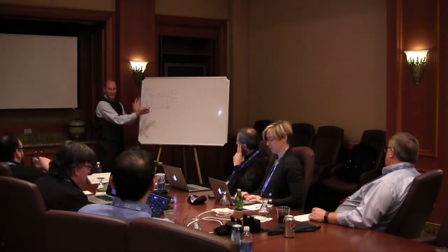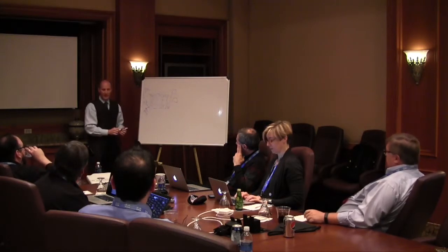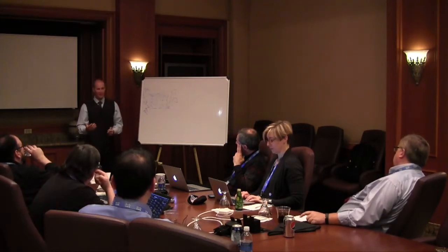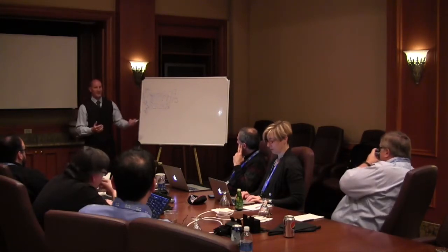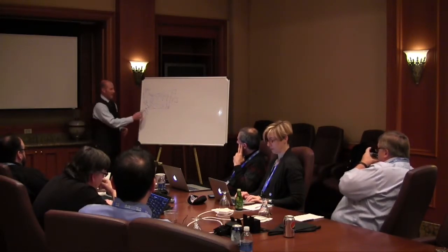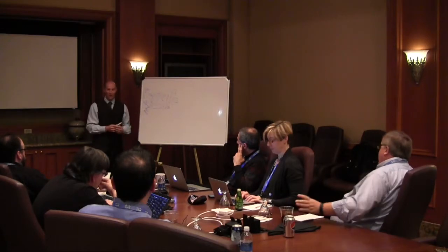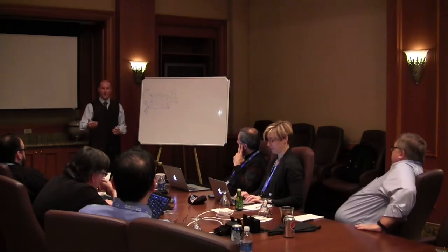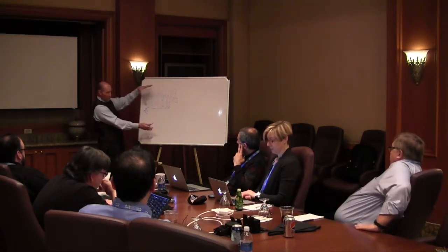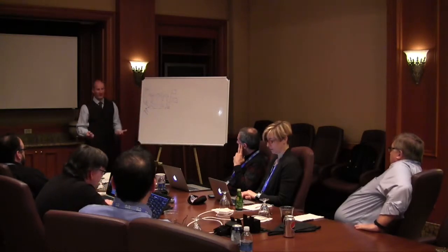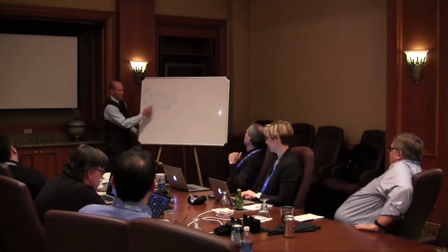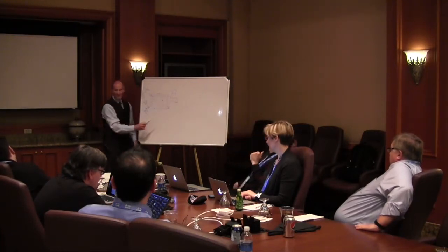And the size of this node, the reason it's 4x4, 16 rack, it's got nothing to do with scale limitations or anything else. This is literally a design concept. Because as I get beyond a 4x4, I start to push out beyond 3 hops. If I have 200 of these and I need to go from here to here, I'll be hopping all day to get to it. 3 hops is a pretty reasonable limit. So if I want to get out of the 3 hop, I pop up and back down into the next node.